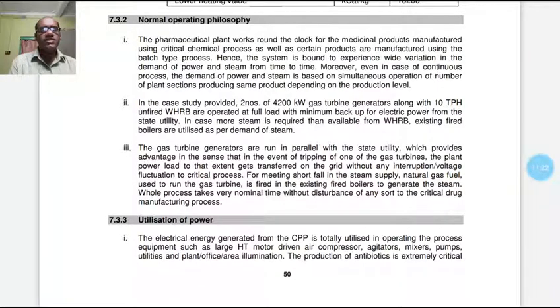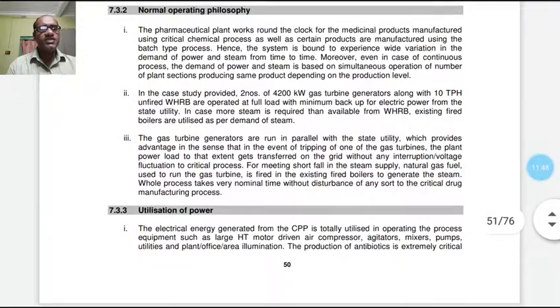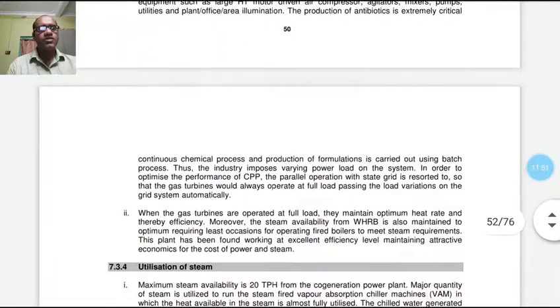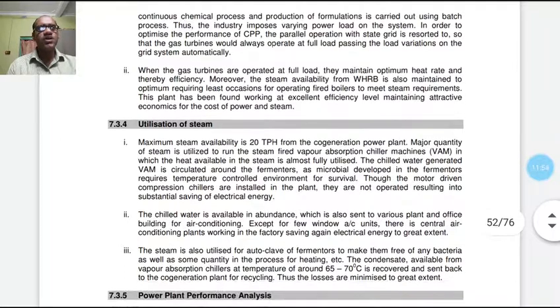Now, utilization of power. The electrical energy generated from the captive power plant is totally utilized in operating the process equipment such as large HT motor driven air compressors, agitators, mixers, pumps, utilities and plant office area illumination. The production of antibiotics is extremely critical. Continuous chemical process and production of formulation is carried out as batch process. Thus, the industry imposes very varying power load on the system.